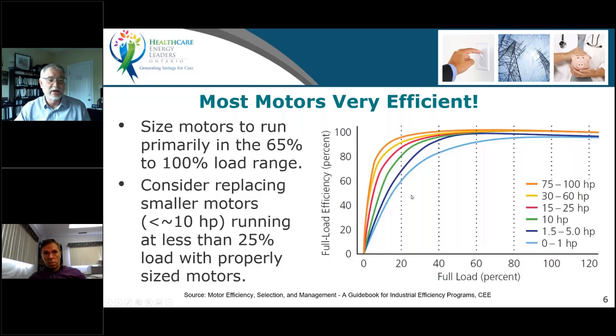So if you do have a motor that's way oversized to its load, to its pump, and you know that for sure, and you know it's not a variable load on that pump of any sort, then you might want to consider resizing that motor to the pump. But I would never start with the motor in terms of changing it. To me, that's the last consideration. So if we work our way back up, and we've got a smaller pump, and now our motor's too big, that's when we want to consider that. And there could be some improvements there. But we have to be careful, because smaller motors are inherently less efficient to begin with. And sometimes you can end up resizing to a smaller motor and actually having lower efficiency, even though it's higher loaded. So it's a bit of a tricky one.